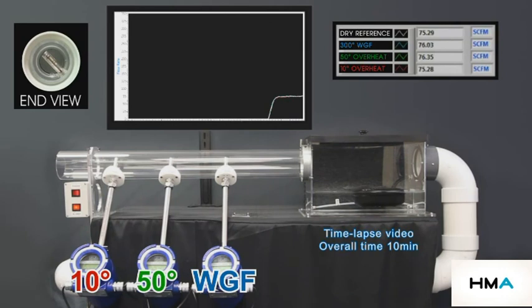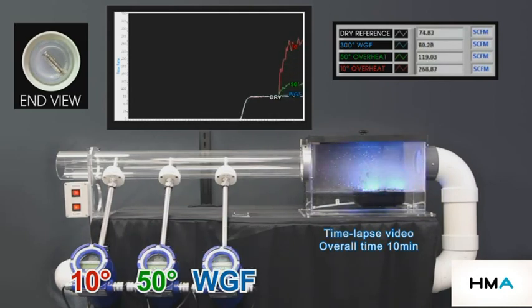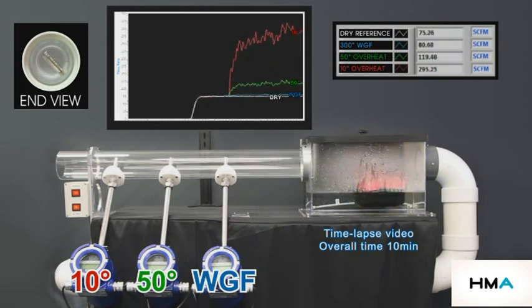At startup when the air flow is dry, all three meters match the dry gas reference meter. Once the fogger is turned on, meter 10 and meter 50 immediately start producing false high readings because the meter electronics interpret the water hitting the sensors as dense gas.